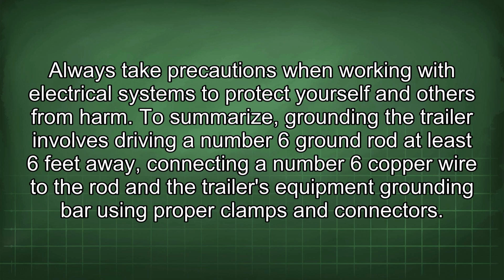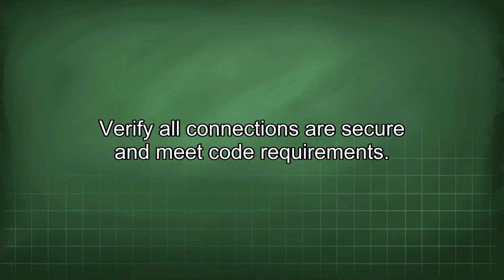To summarize, grounding a trailer involves driving a number 6 ground rod at least 6 feet away, connecting a number 6 copper wire to the rod and the trailer's equipment grounding bar using proper clamps and connectors. Verify all connections are secure and meet code requirements.